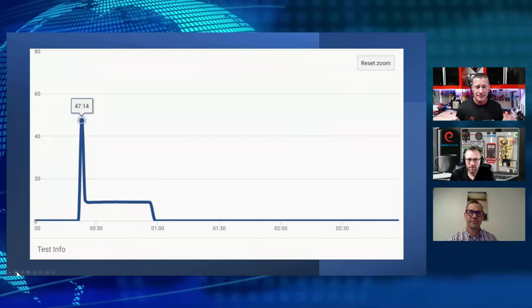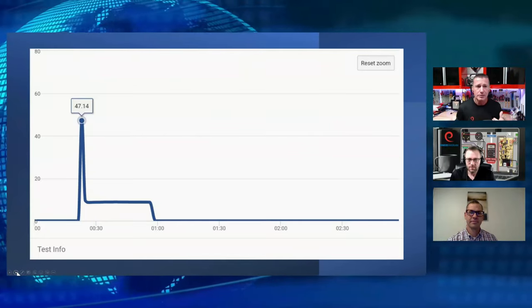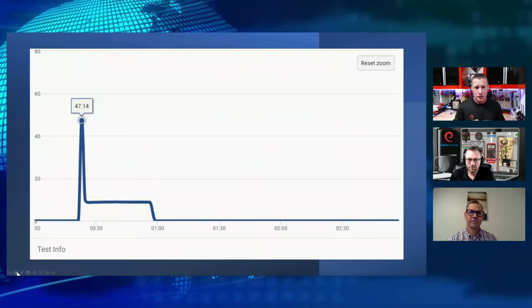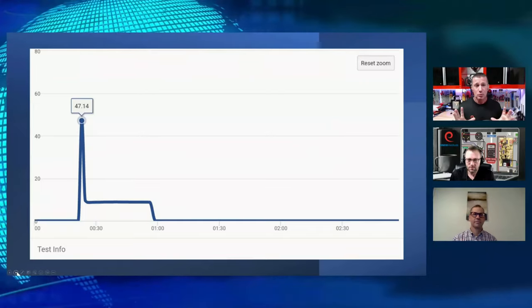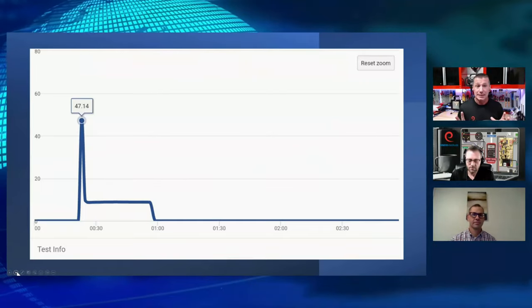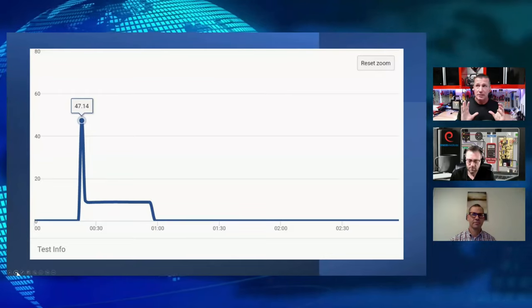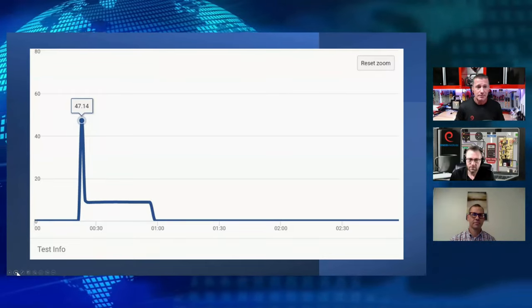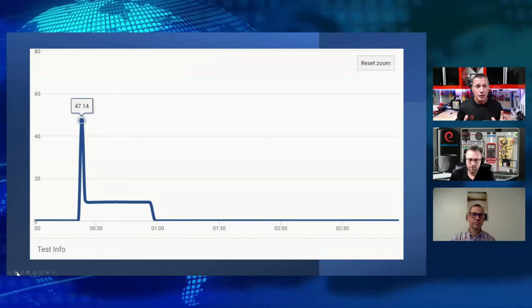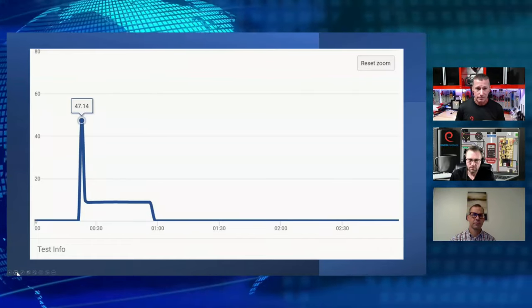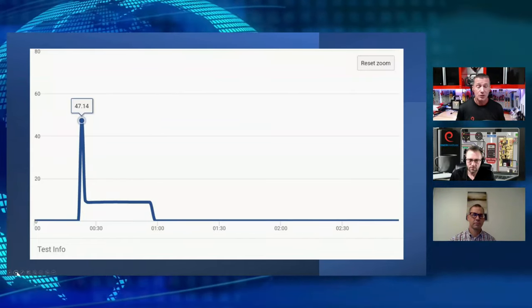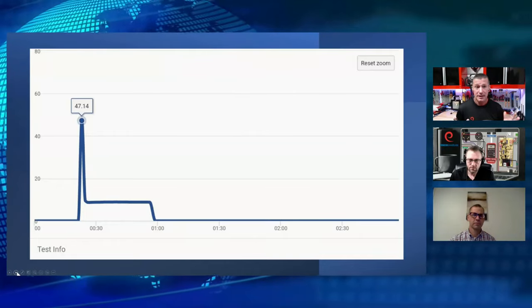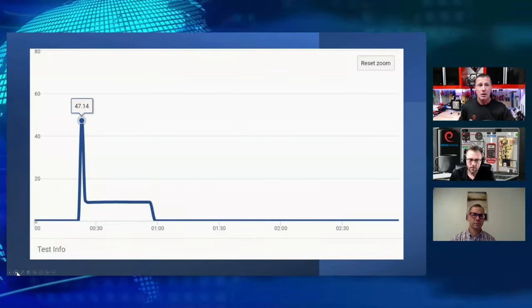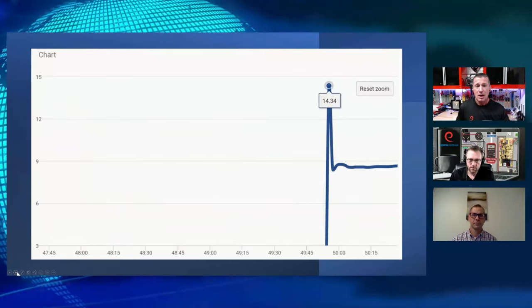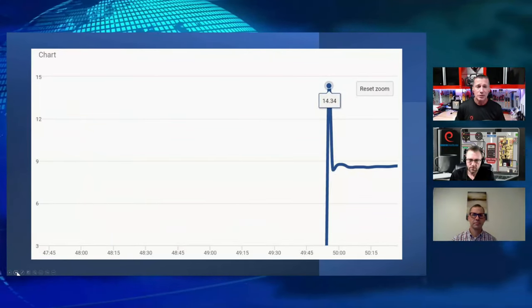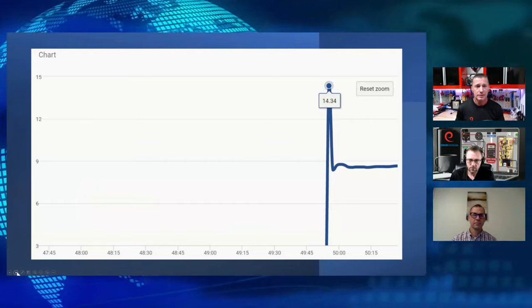So on my 14 SEER R410A system, it's about 3 years old. I had an inrush current, and a lot of people don't realize how much current we draw on PSC motors on startup. It's pretty significant. On this 3-ton 14 SEER, about 3 years old, I drew an inrush current of about 47.14 amps on startup, using a redfish meter and doing some data logging. After installing a soft start device on my unit, I was able to reduce that inrush current down to 14.34 amps.